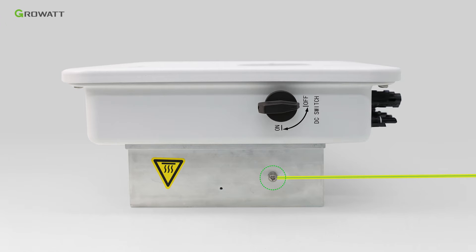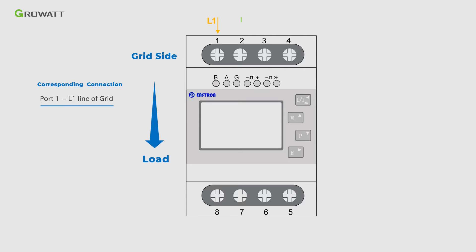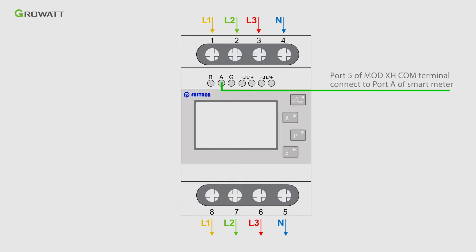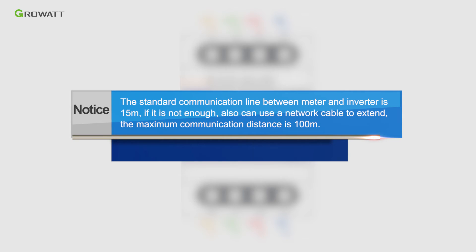Please remember to connect the grounding connector. Connect L1, L2, L3, and N-line of the grid to port 1, port 2, port 3, and port 4 of the smart meter. Connect port 8, port 7, port 6, and port 5 of the smart meter to L1, L2, L3, and N-line of the load. Connect port A of the smart meter to port 5 of the MODXH communication connector, and port B of the smart meter to port 6 of the MODXH communication connector. Note: the standard communication line between meter and inverter is 15 meters. If not enough, a network cable can be used to extend it — maximum communication distance is 100 meters.